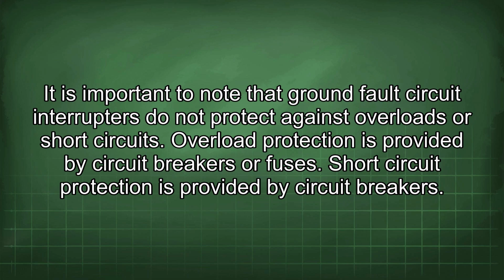It is important to note that ground fault circuit interrupters do not protect against overload or short circuits. Overload protection is provided by circuit breakers or fuses. Short circuit protection is provided by circuit breakers.